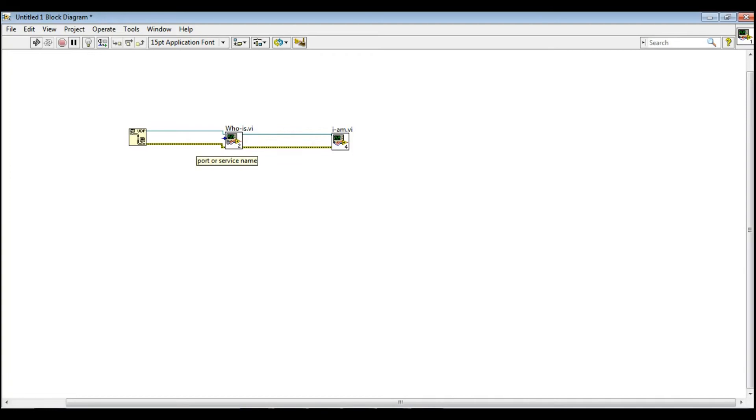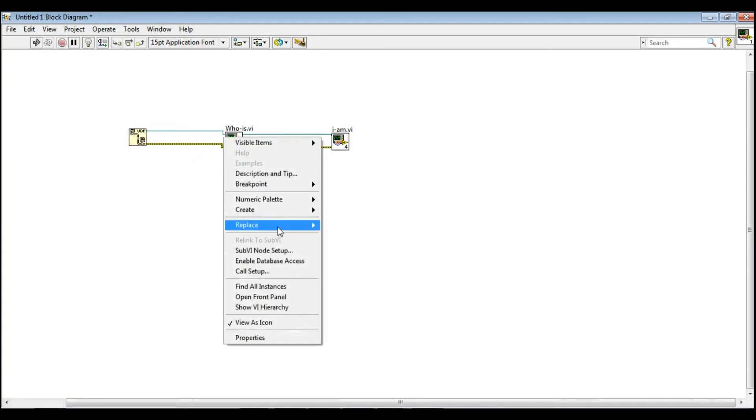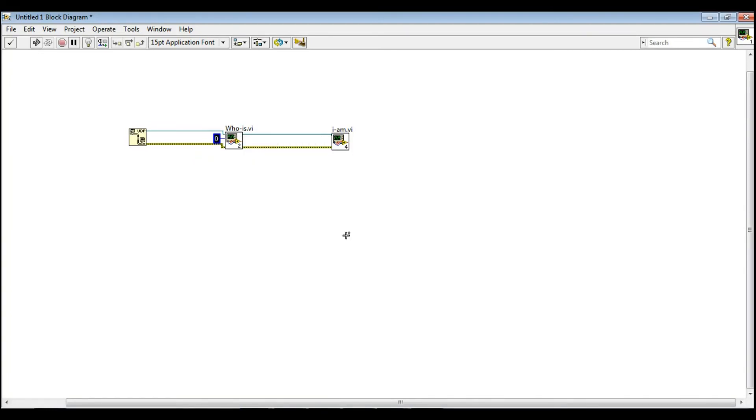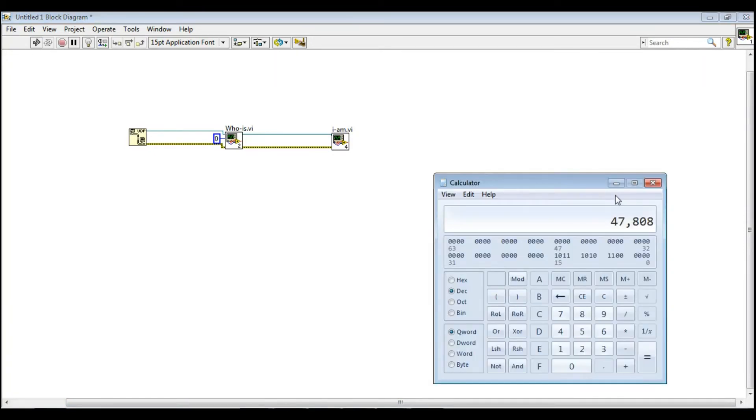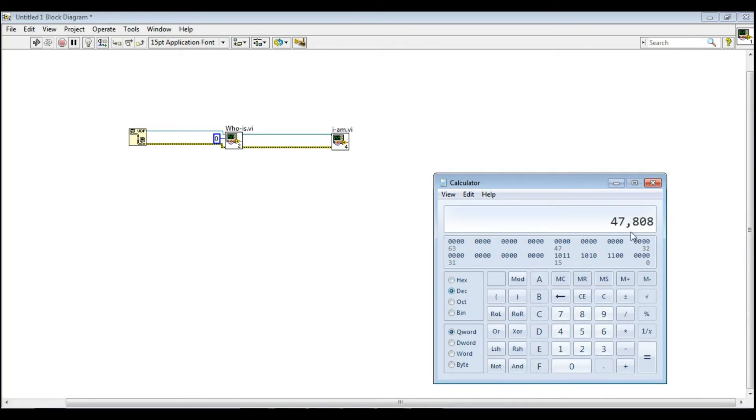The UDP source and destination port shall be set to BAC0. If we convert BAC0 in decimal, it will be like 47808.